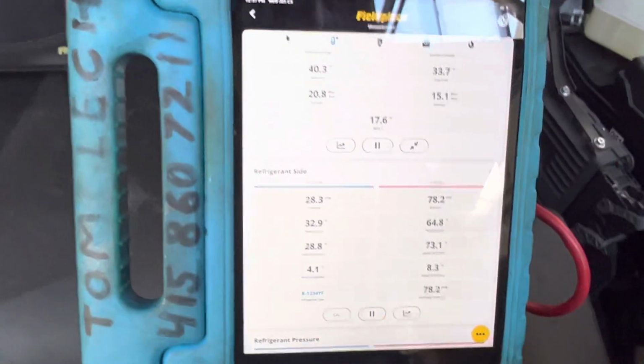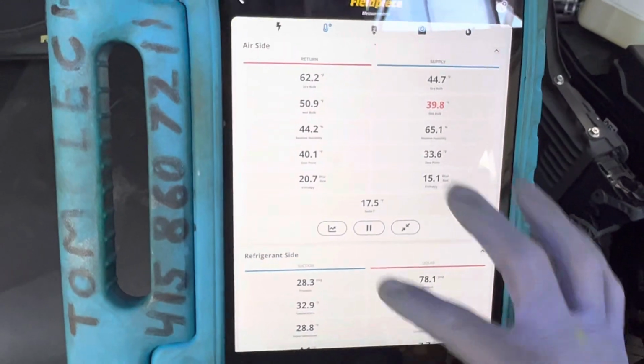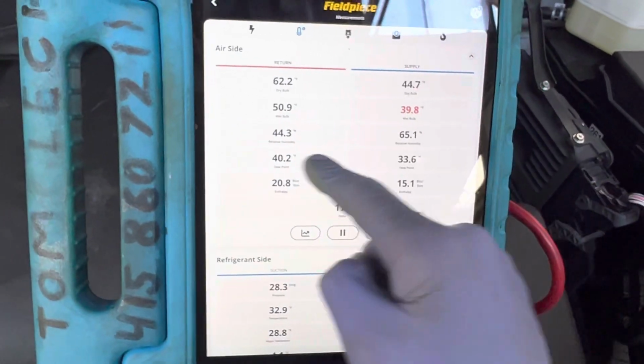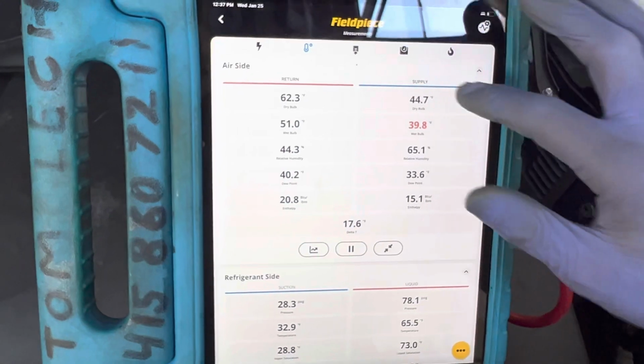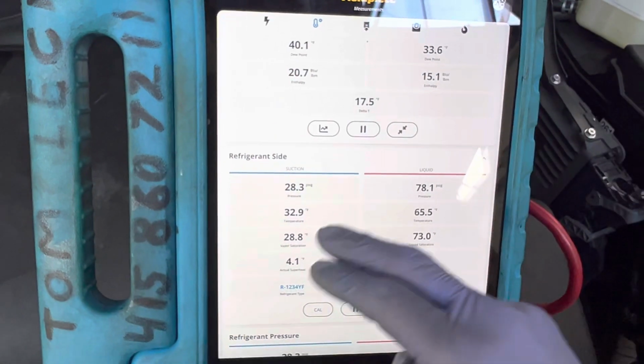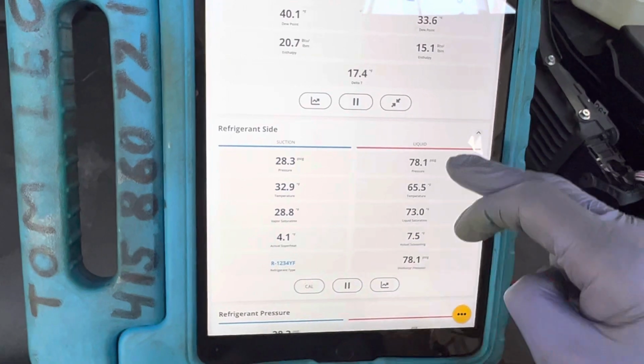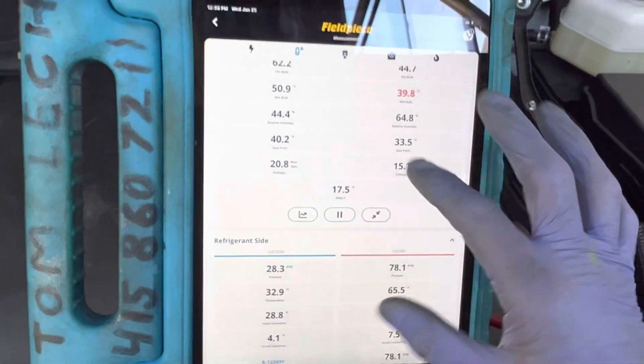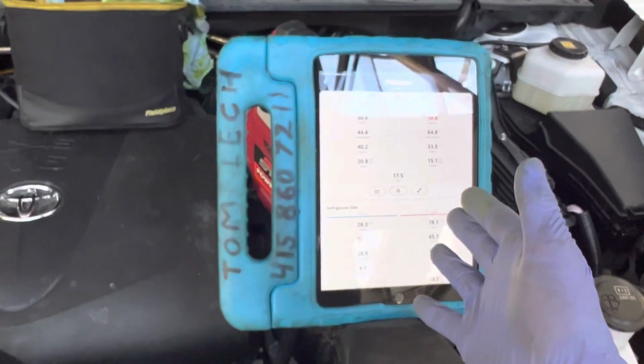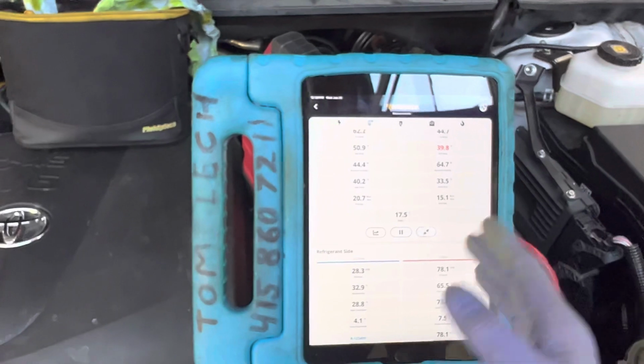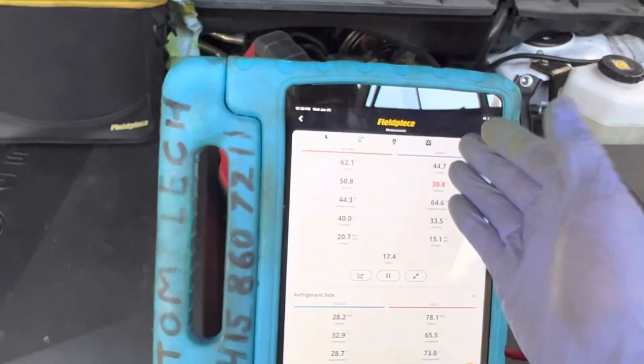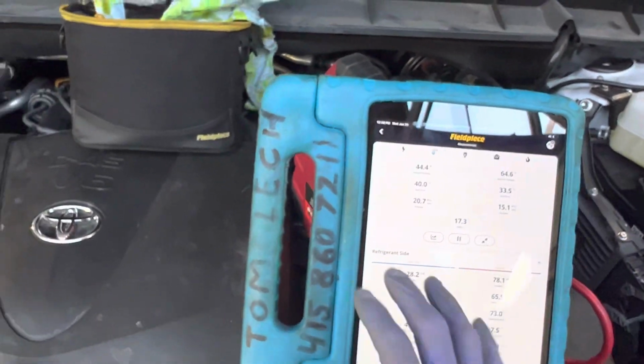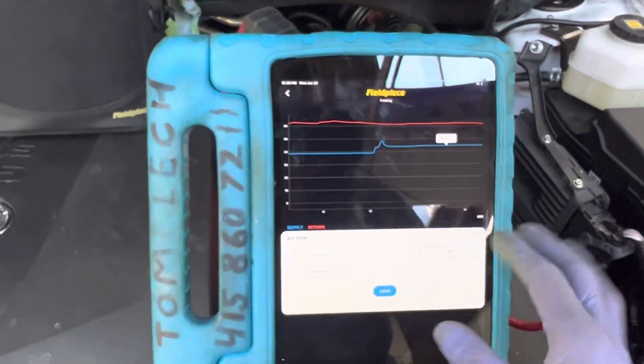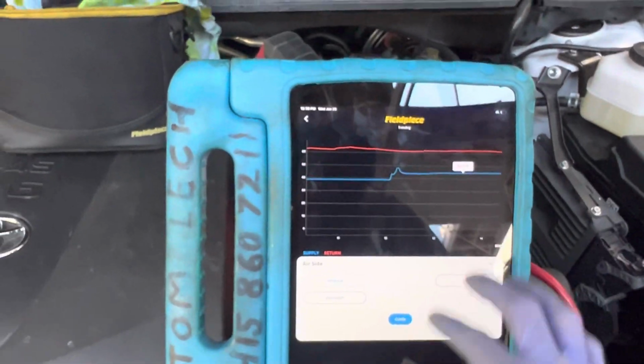So that's it. I'll let you see this one more time. We've got the air side, the humidity, the dew point, our wet bulb or dry bulb. You can see we're on YF refrigerant, and you can see everything here. This gets recorded and it goes onto your customer's invoice, to your customer and for you for future reference. And if you ever have anyone dispute what you actually did and how you delivered to the customer, you have the proof right here because it's live running with Bluetooth sensors, data logging, everything, and you can always go back and look at it.